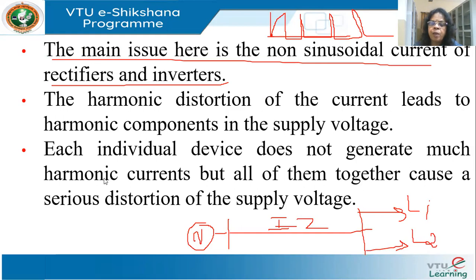Let us say load one is driven by power electronic converters - all the drives there, maybe a small steel mill, cement factory, or textile mill. Load two is predominantly sinusoidal, drawing unity power factor or low power factor current with no corruption. Load one draws harmonic currents because of rectifiers and inverters, whereas load two draws only fundamental current. Don't confuse this with power factor - I'm only talking of the frequency of the current.